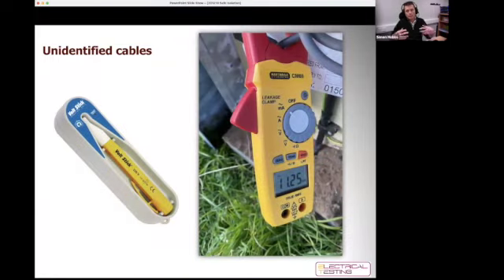Now, there are steps that we can move through. So if the cable cores are accessible, as in the picture on the right here, we could use a clamp meter, and we can use that to see if there's any current flowing in the cable. Any current flowing indicates that obviously the circuit is live and it's being used and it's drawing current on a load. A non-contact voltage indicator, shown on the left here, can be useful in these situations to make a preliminary test for voltage. But these can only be used where we haven't got a metallic sheath. So it can show where it's live.